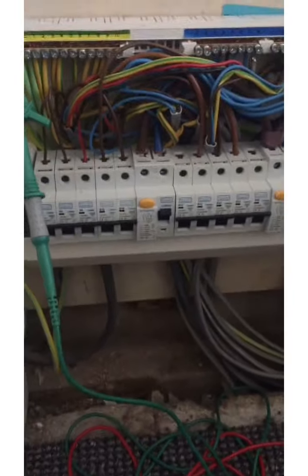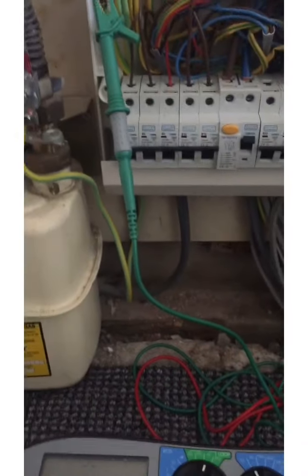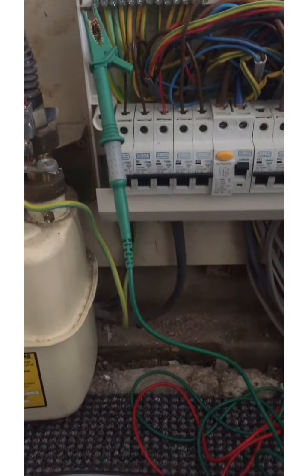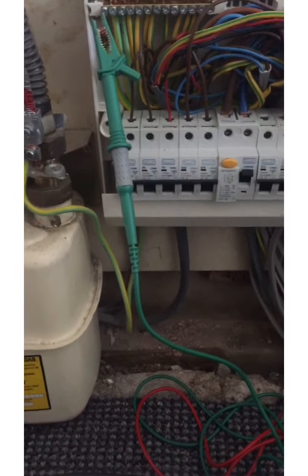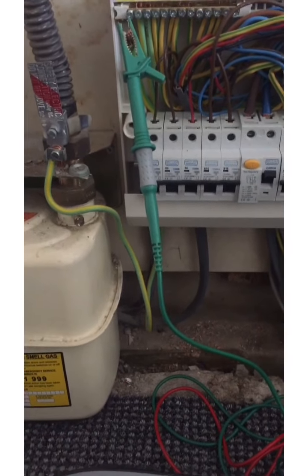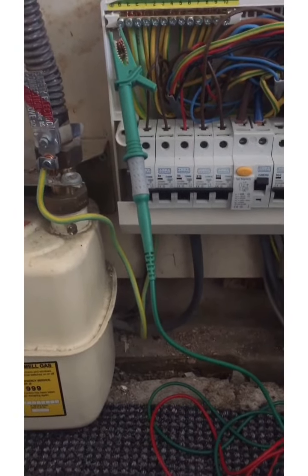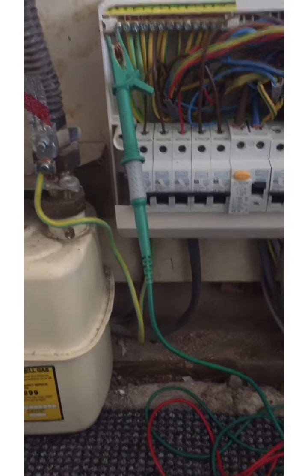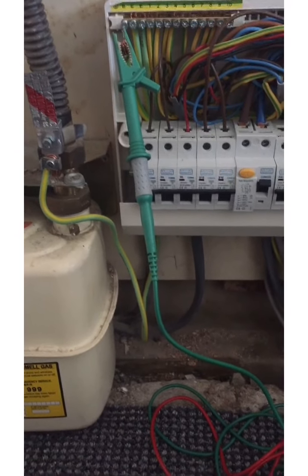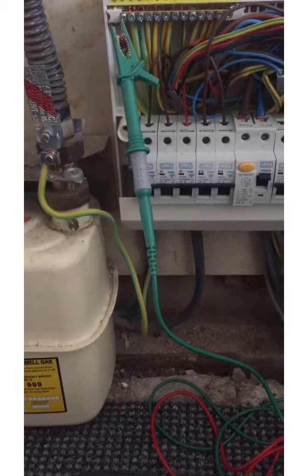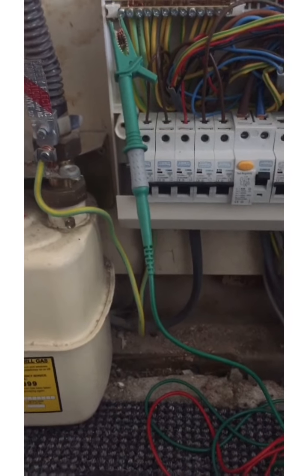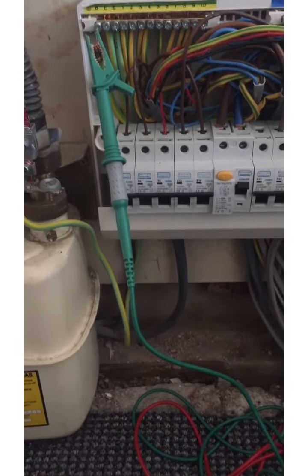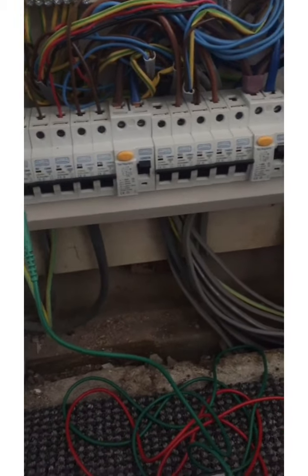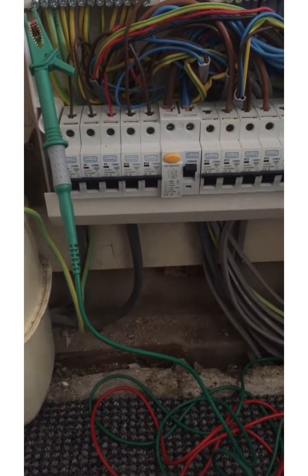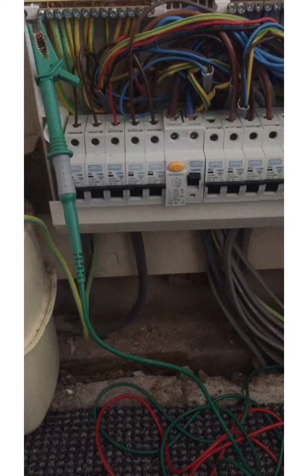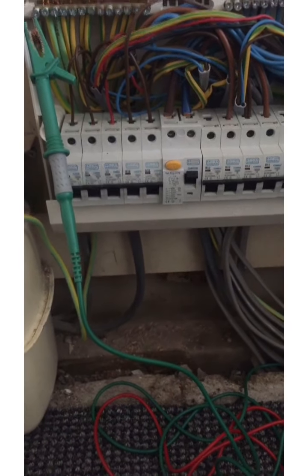Now, a couple of things. The Electricity at Work Regulations basically says, summing it up here, that we do live tests if there's no alternative. Here, the only way that we can take a measurement of the ZE is to do a live test. So this is one of those situations where there is no alternative. The other thing is that you'll see when I put the line probe on that I'm using GS38 approved test leads, and that's the subject of another video.